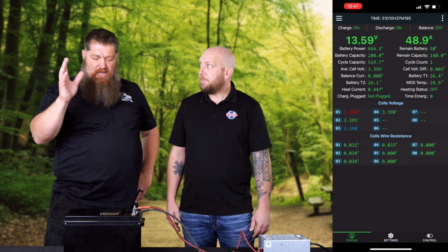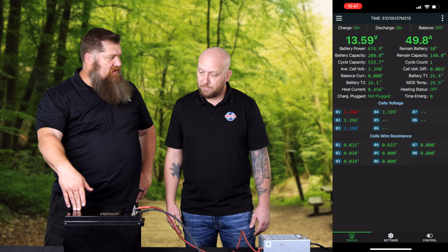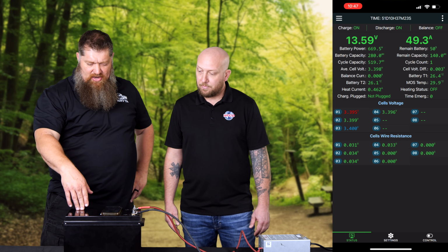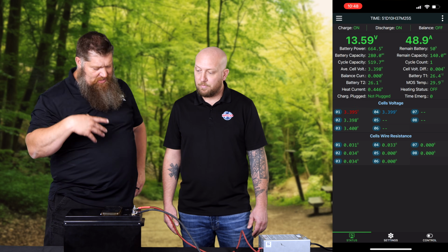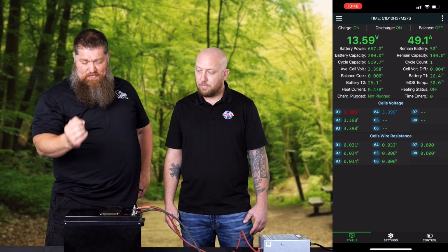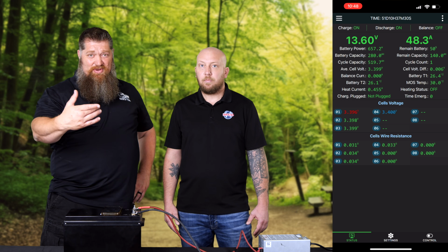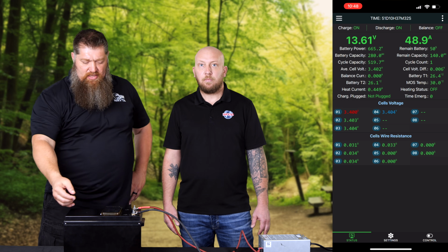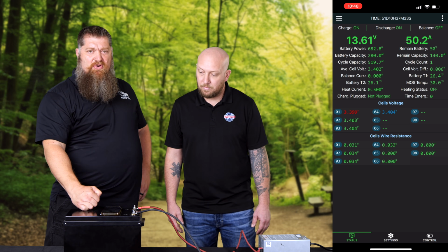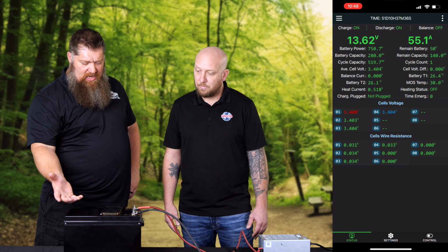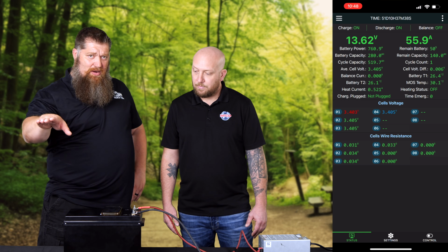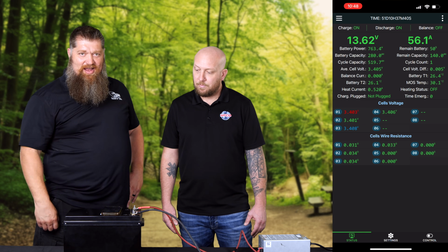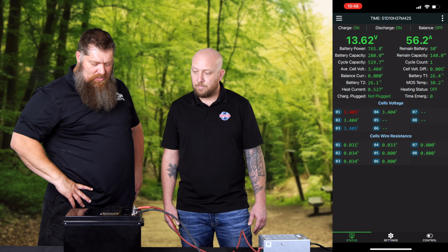So right now, what we're confirming is we are charging at 50 amps. On this 300 amp hour battery, it would take about 6 hours if it was completely dead. Put that on a lead acid battery, and you're still looking at between 8 and 12 hours because of the slope. We still have 13.61 volts, right, and we're going to see that until this amperage begins to cut off - then we'll see the voltage shoot up.